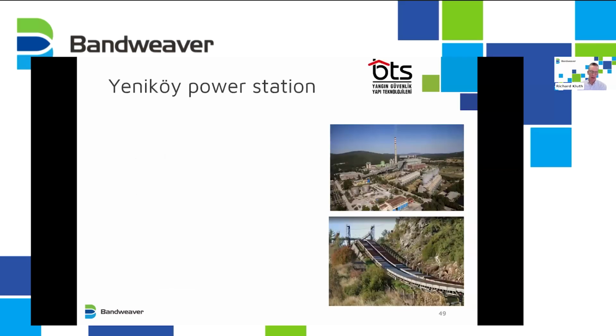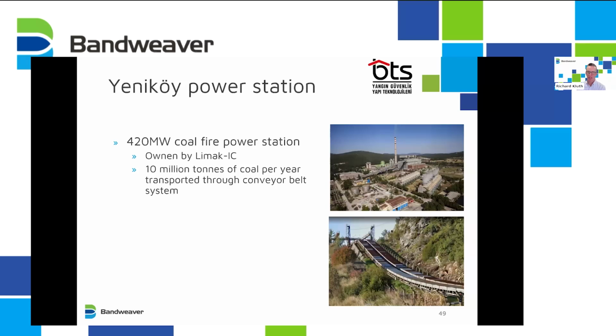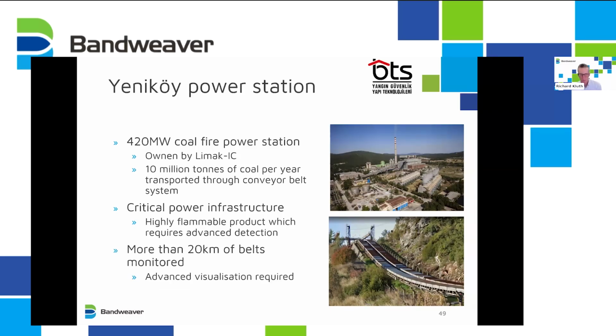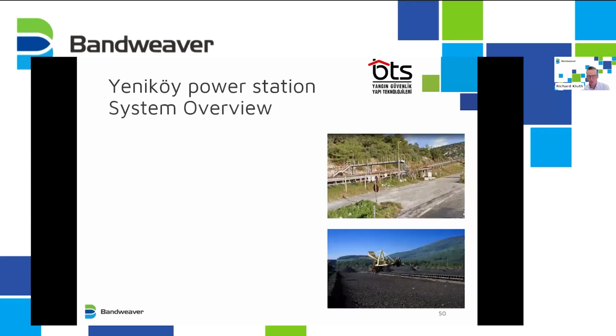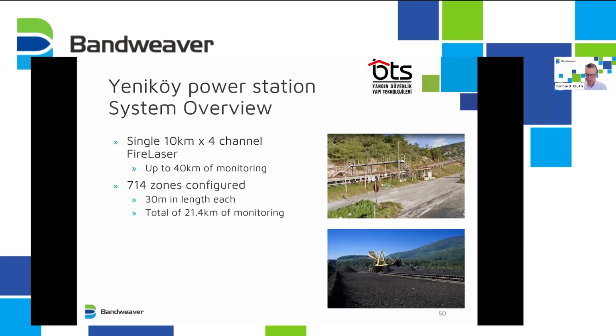Moving on from road tunnels, looking at conveyor belts in a power station. This is a coal fire power station. A lot of coal moves through critical power infrastructure, the highly flammable product. More than 20 kilometers of belts involved in this. They needed advanced visualization, which we won't go into in this presentation. It was based on a single 10-kilometer unit with 4 channels, so you could have up to 40 kilometers. They configured 714 zones, each 30 meters in length, so they used about 50% of the capacity.